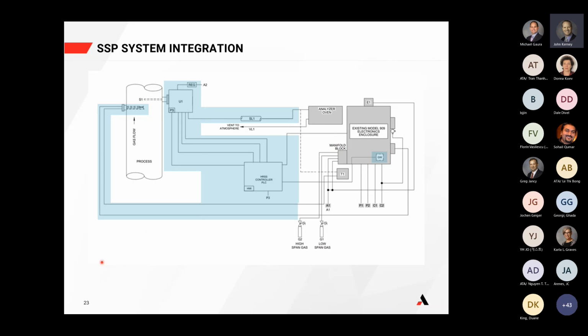And then there's several questions around temperature and the controller and the probe. So maybe I'll try to group a few of these together. One question was, are temperatures controlled to the set point using electrical tracing on the probe and sample lines and electrical heaters inside filters, controllers, etc.? So the sample line is actually heat controlled by the analyzer. The analyzer controls the sample line set point. The probe heater has its own element within the probe itself. The probe filter has its own element within the probe filter.